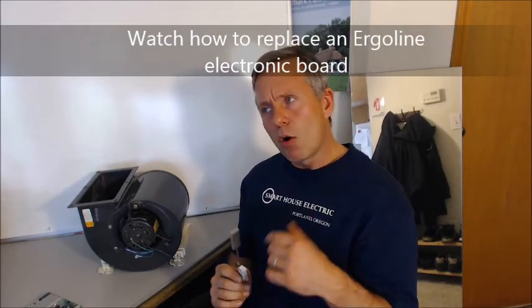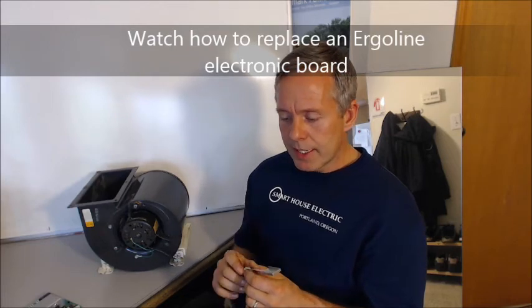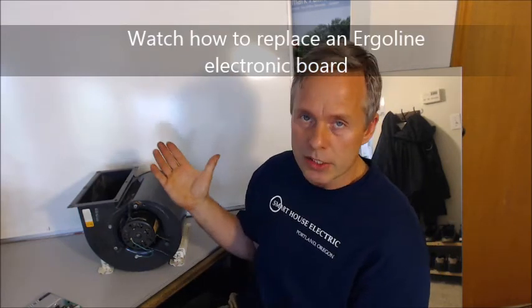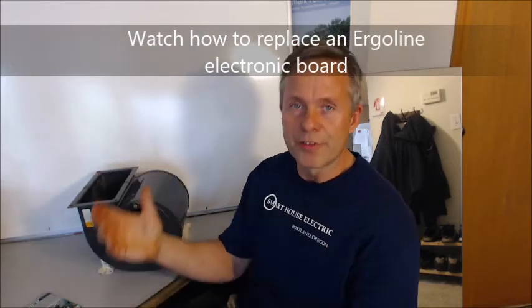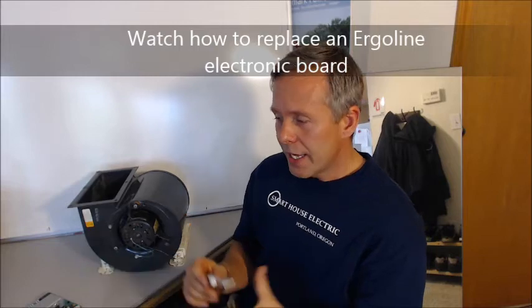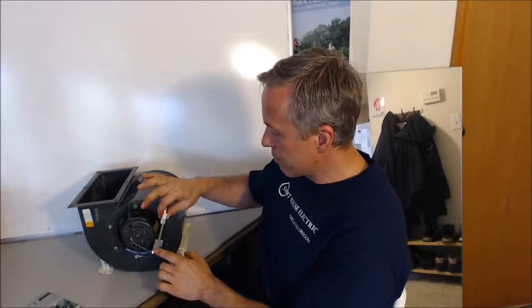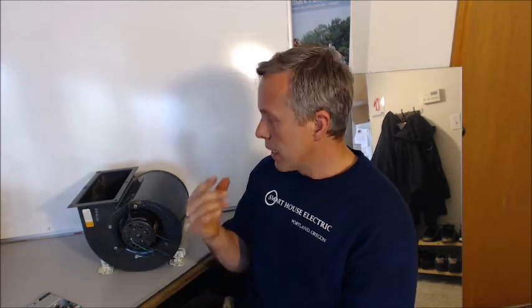41 is basically the opposite, and that is that after your aftercooling has finished, which is that 3 minutes of cooling of the fans that goes after the session, if you still have this airflow switch engaged after 1 minute, it's going to give the error code 41. And that means that it could be that you actually have airflow. So again, when you have this problem, check if there's air coming through the machine. Because if you do, then this could mean that a fan board is defective, and it's constantly asking the fan to run.